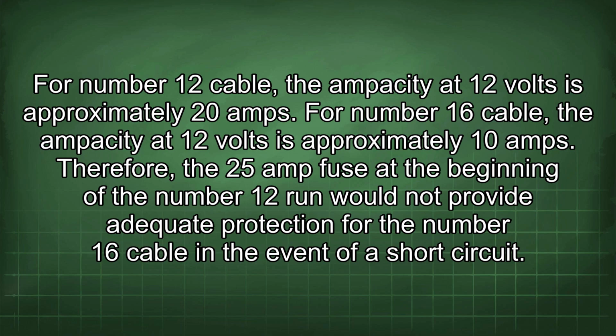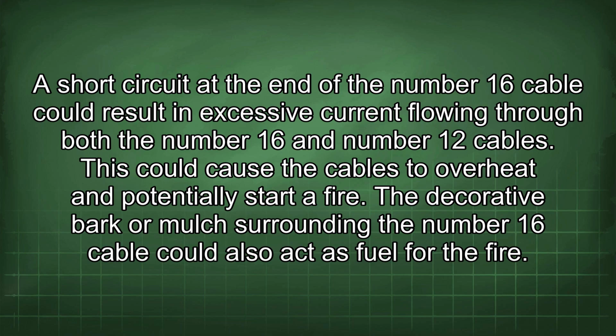Therefore, the 25 amp fuse at the beginning of the number 12 run would not provide adequate protection for the number 16 cable in the event of a short circuit. A short circuit at the end of the number 16 cable could result in excessive current flowing through both the number 16 and number 12 cables. This could cause the cables to overheat and potentially start a fire. The decorative bark or mulch surrounding the number 16 cable could also act as fuel for the fire.